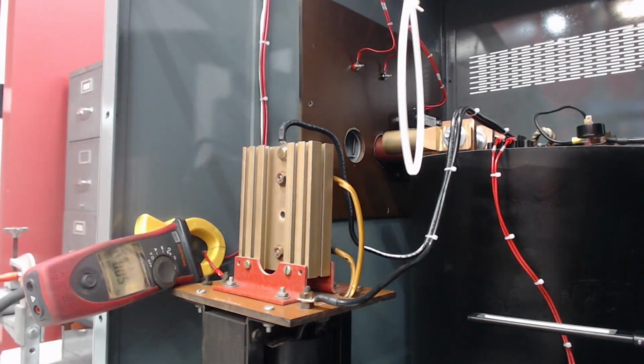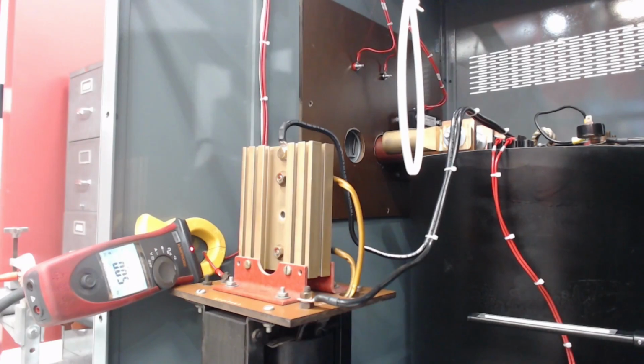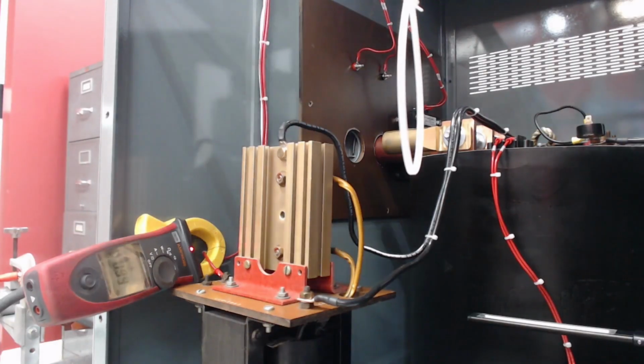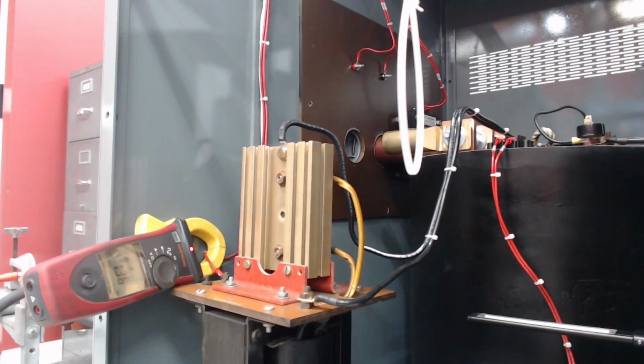So if I turn the unit on, the unit is on now, and now I'm going to ramp up. We are going to begin to see a little bit higher usage there, linearly rising with the increase of output. Once again, that shouldn't exceed anything on the output side. It may not be the same as your input because there is a transforming conversion there, but you should not be exceeding anything on the output. If you are, then you'll need to deal with that math and figure out what's going on. Could be the diodes, could be something else, but most likely it's going to be the diodes on that transformer, because it's just a basic transformer, and then those diodes are rectifying. So that's pretty much it at this point.